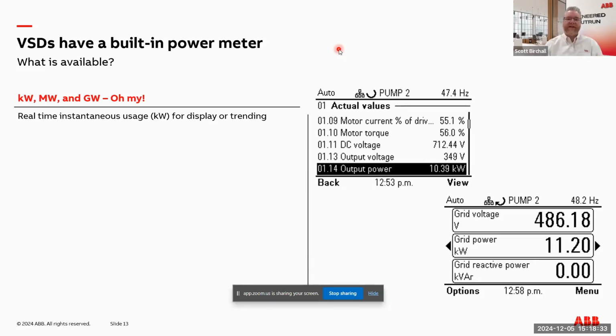I get energy savings. I can speed it up. I can slow it down. I can control flow. But you're not using the full value of a drive. And the things I'm going to talk about, these screenshots are coming from an ABB drive, because that's just the drives I've got, and that's where I'm employed. But I'm not really sharing things that are unique to ABB. This type of concept is also available whether you've got brand A, brand B, or brand C drives. This isn't one brand or another. So this is drives in general.